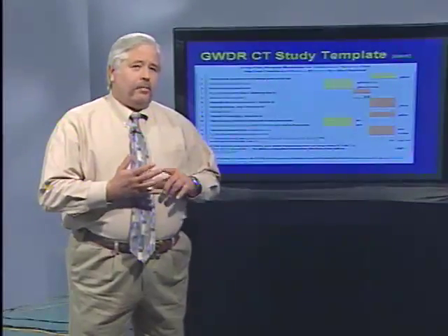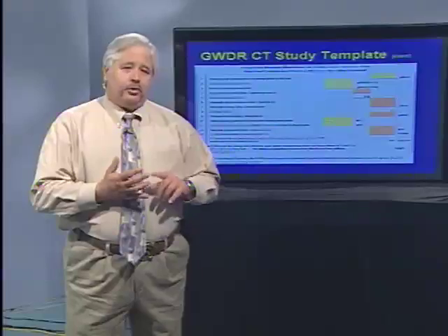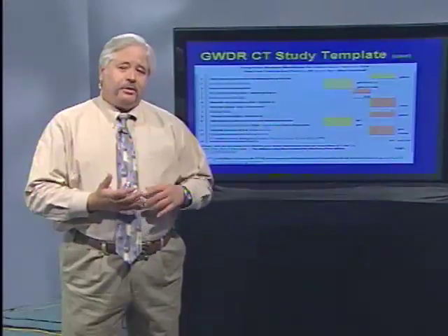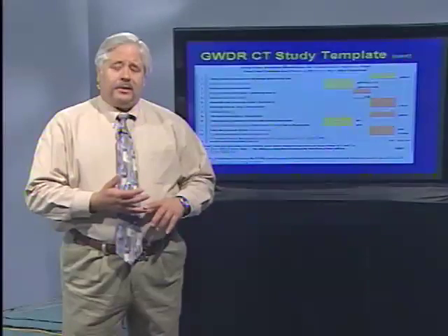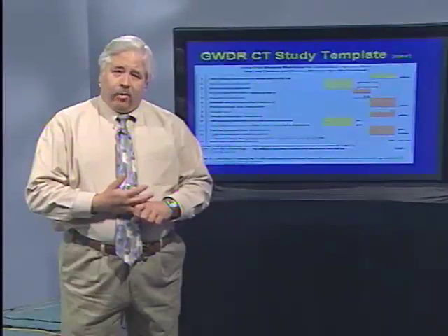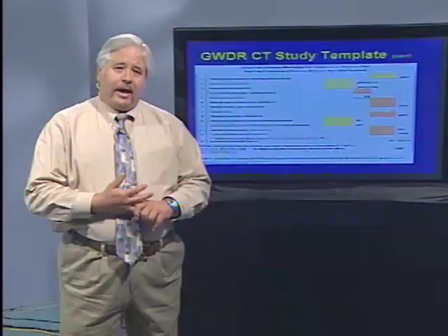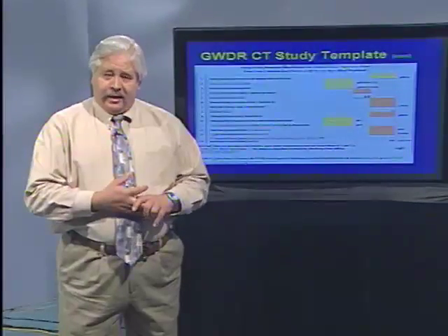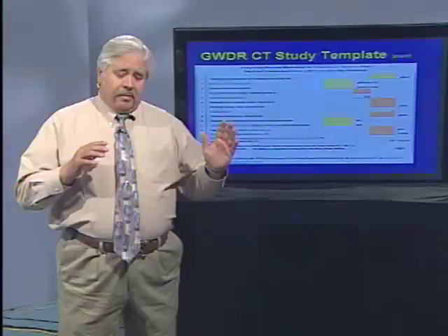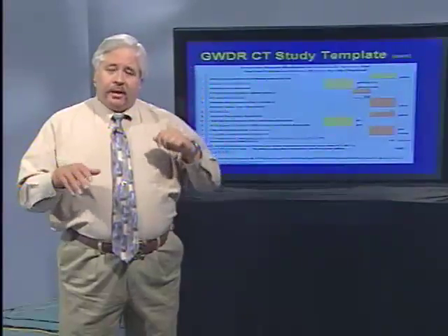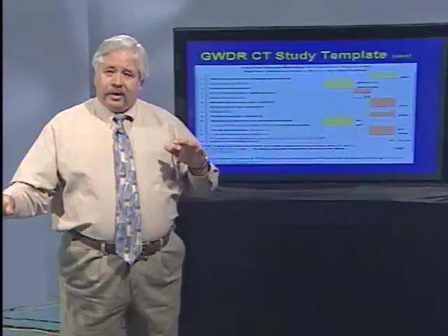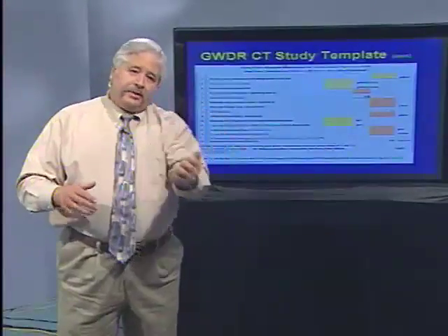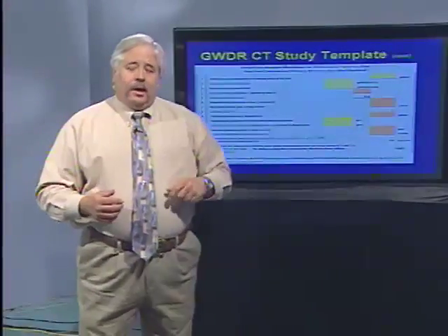It's dealing with plants that are treating groundwater, as we already talked, groundwater not under the influence. It's treating plants that are using free chlorine for their 4-log viral inactivation. They've got ground storage tanks or some other storage contact vessel. The inlet for the storage vessel and the outlet for the storage vessel both exist. That is, they don't use the same line to fill the tank as they do to draw water from it.